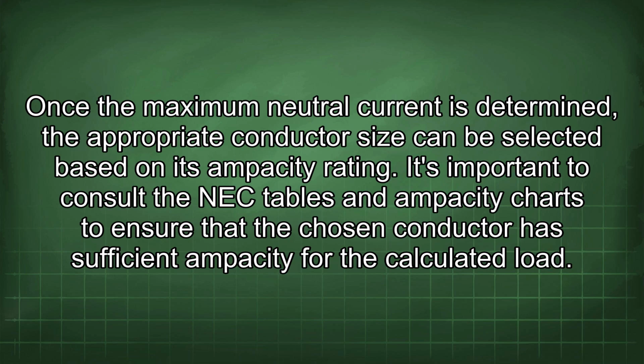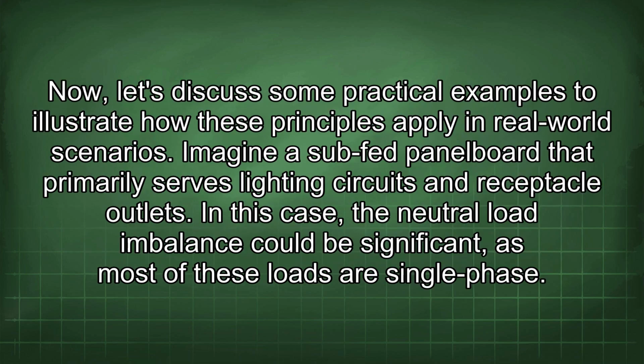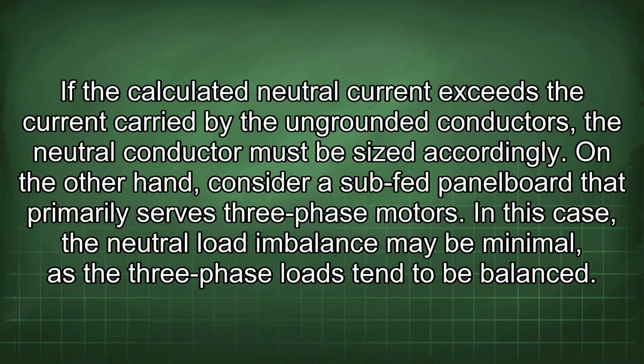It's important to consult the NEC tables and ampacity charts to ensure that the chosen conductor has sufficient ampacity for the calculated load. Now, let's discuss some practical examples to illustrate how these principles apply in real-world scenarios. Imagine a sub-fed panel board that primarily serves lighting circuits and receptacle outlets. In this case, the neutral load imbalance could be significant, as most of these loads are single-phase. If the calculated neutral current exceeds the current carried by the ungrounded conductors, the neutral conductor must be sized accordingly.